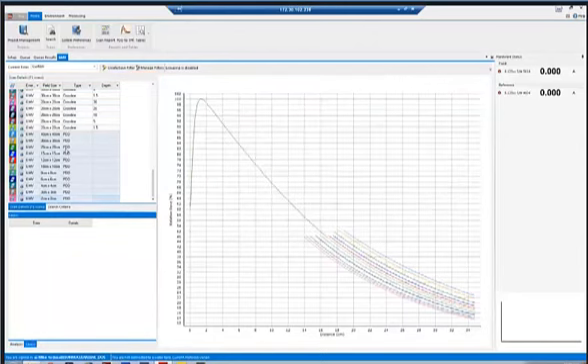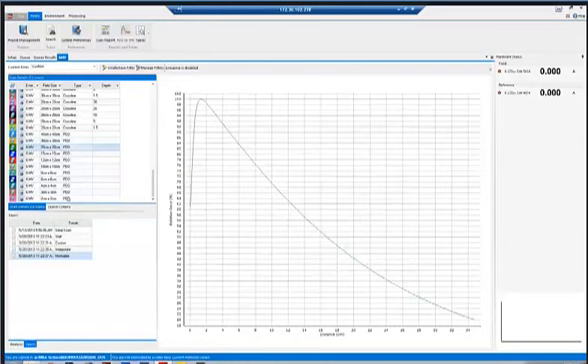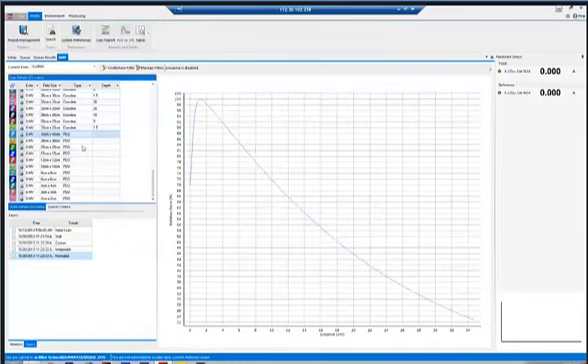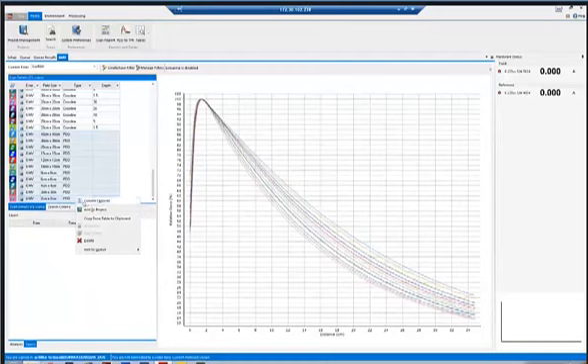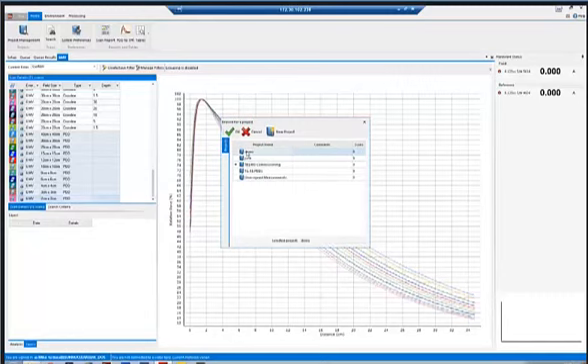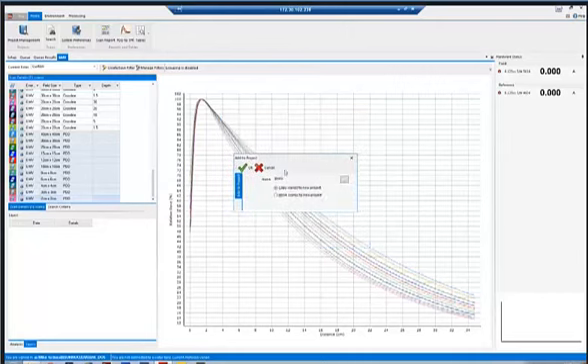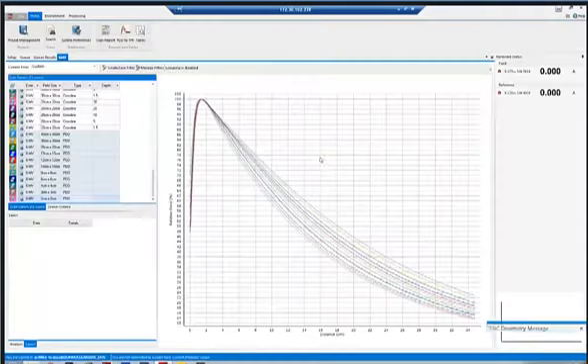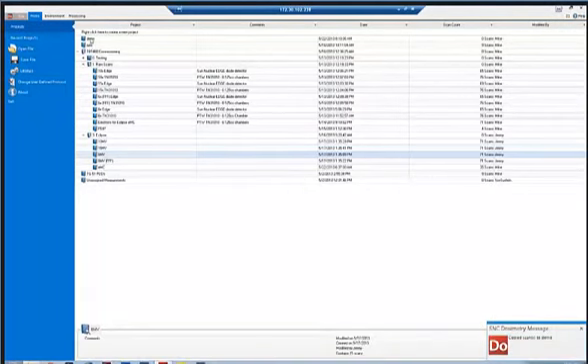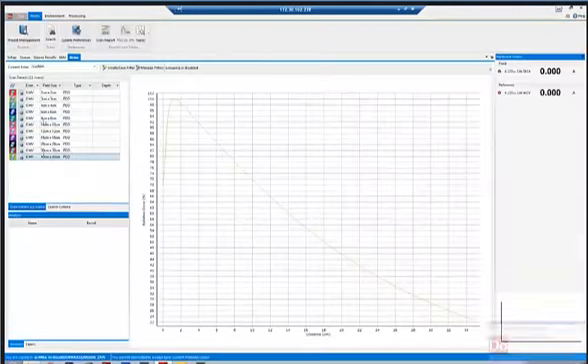We could come in here and look through our scans. We can sort them by type. We can sort them by energy. In this case, we've done the sorting by energy just simply using the project label. You can come in here and look at all of your scans, see how they compare to one another, see if they follow any trends. If you've scanned with the chambers of different volumes, they end up having gain issues down at depth. So you want to make sure that these are all tailing off the same way. So you can end up doing various things with your scans and views of your scans. You can process them. You can look at the layers for a particular scan. So in this case, if we wanted to play with these scans, we don't have to mess with the ones we've already done. You can just say add to project.